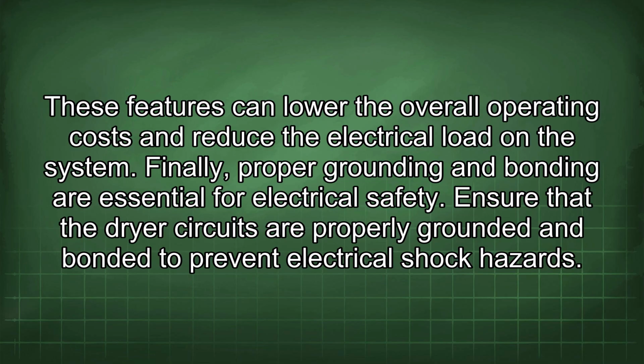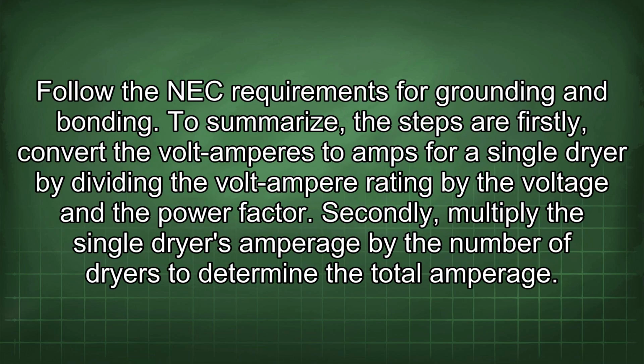Finally, proper grounding and bonding are essential for electrical safety. Ensure that the dryer circuits are properly grounded and bonded to prevent electrical shock hazards. Follow the NEC requirements for grounding and bonding. To summarize, the steps are: firstly, convert the volt-amperes to amps for a single dryer by dividing the volt-ampere rating by the voltage and the power factor.